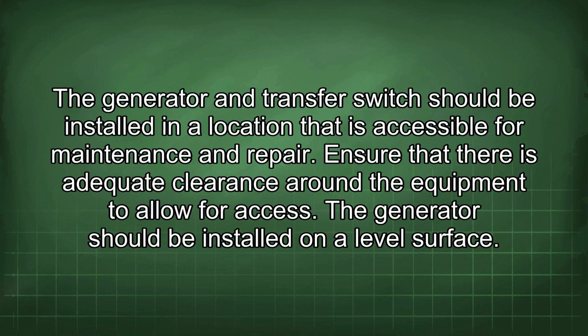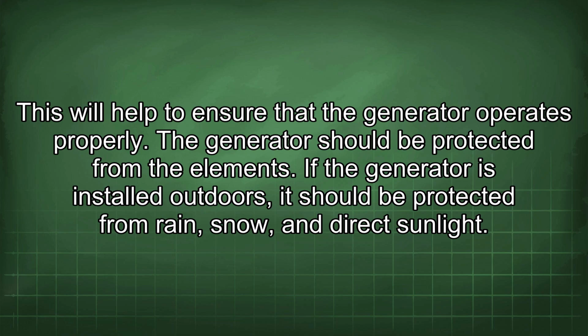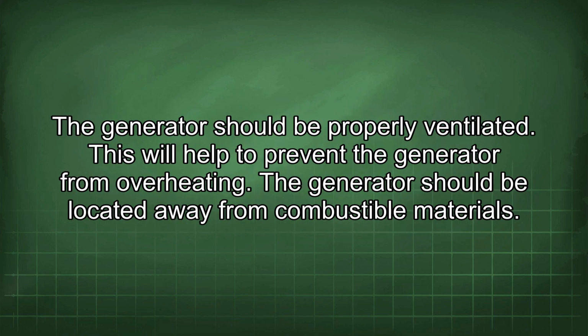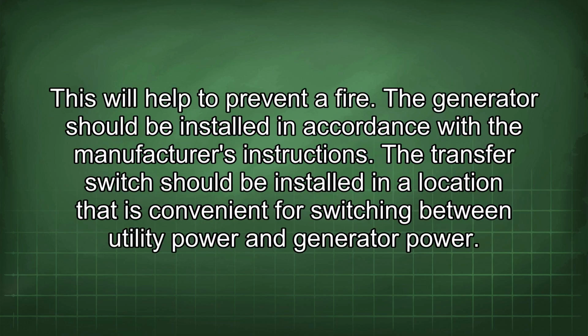The generator and transfer switch should be installed in a location that is accessible for maintenance and repair. Ensure that there is adequate clearance around the equipment to allow for access. The generator should be installed on a level surface. This will help to ensure that the generator operates properly. The generator should be protected from the elements. If the generator is installed outdoors, it should be protected from rain, snow, and direct sunlight. The generator should be properly ventilated. This will help to prevent the generator from overheating. The generator should be located away from combustible materials. This will help to prevent a fire. The generator should be installed in accordance with the manufacturer's instructions.